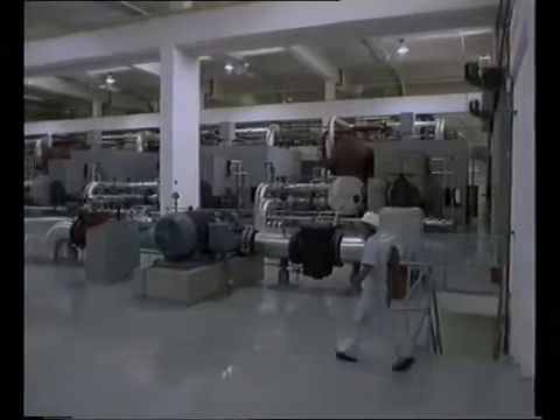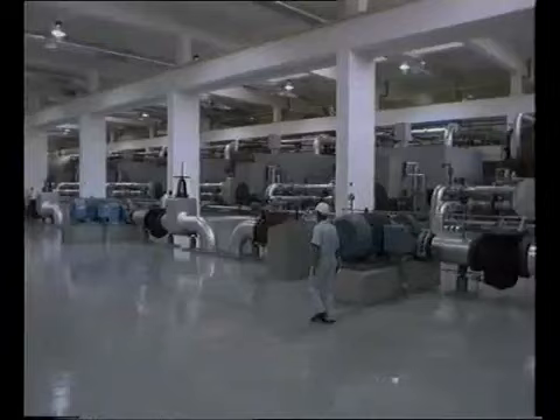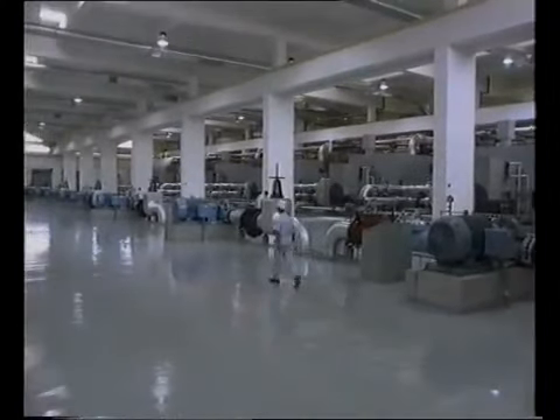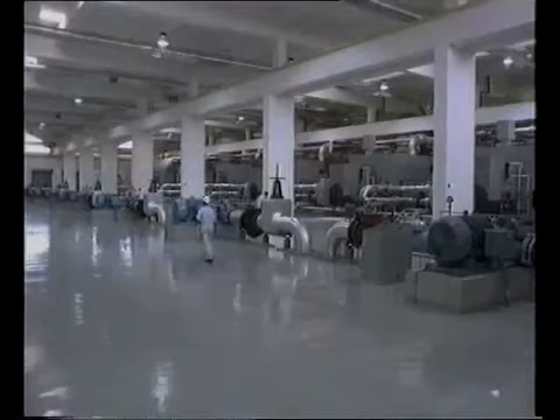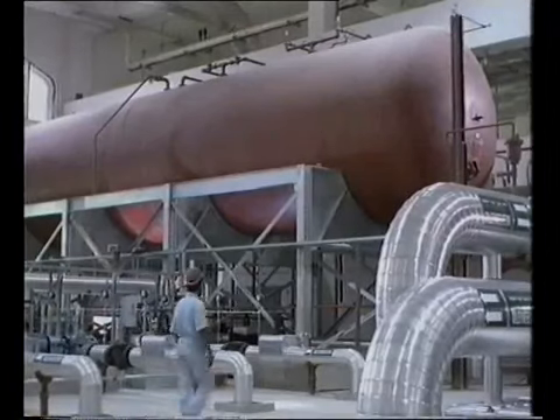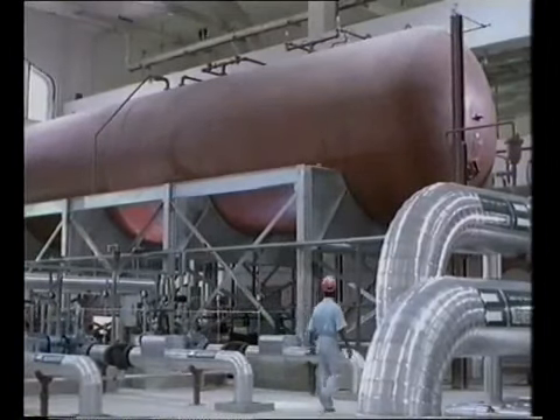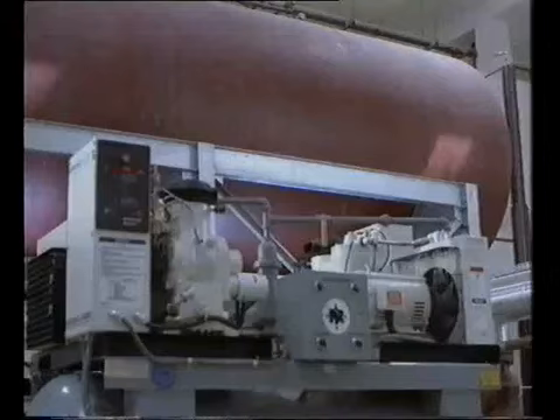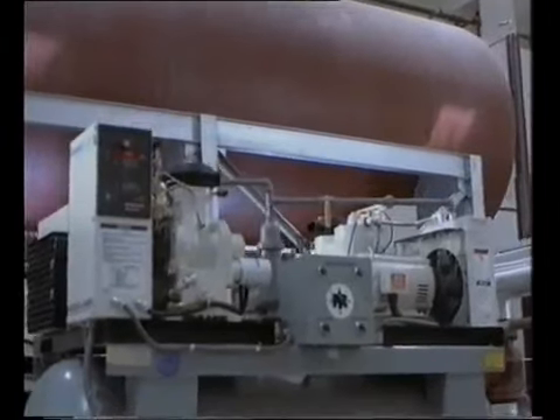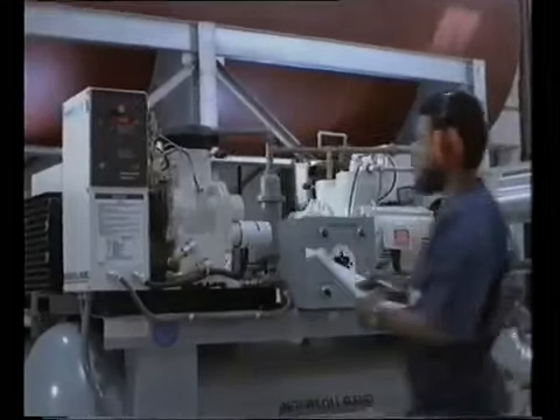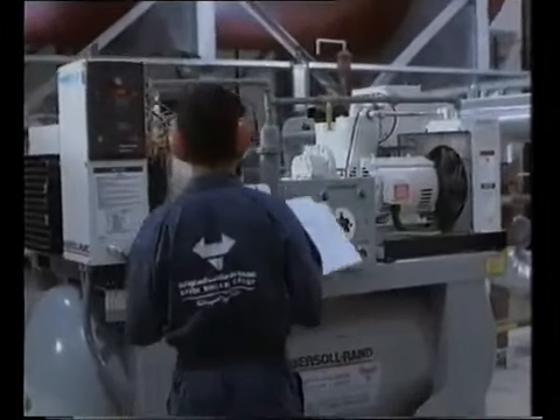The water circulating from the chillers to the Haram basement and back is kept in a sealed system. To maintain the high pressure, which could alter as the pipes expand or contract in the fluctuating temperatures, the system can be topped up with mains water held in a tank under pressure by compressed air.